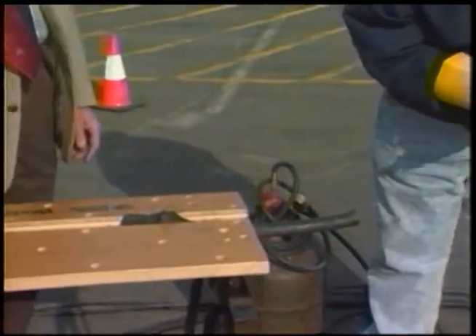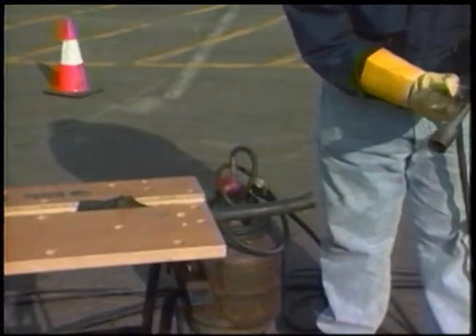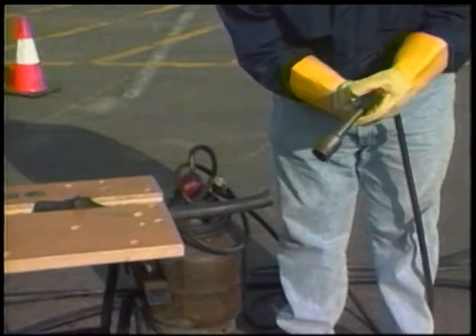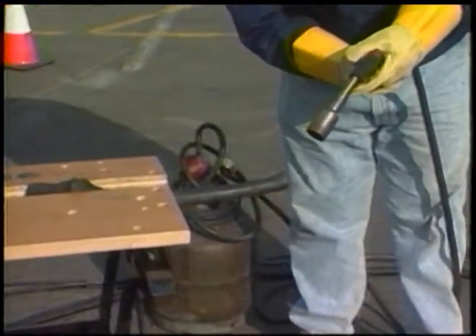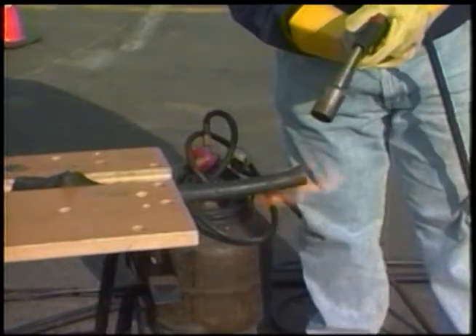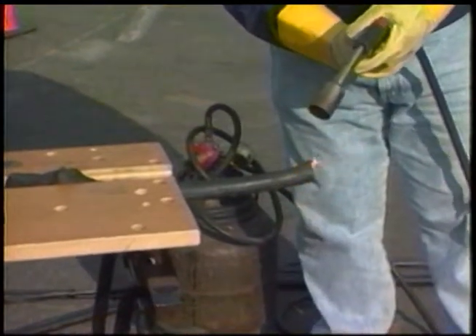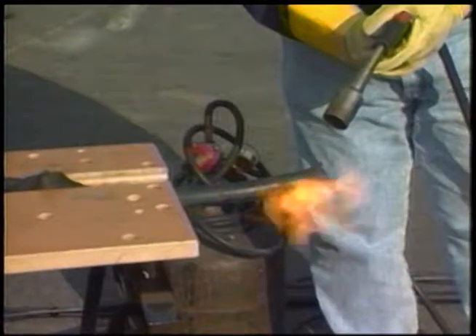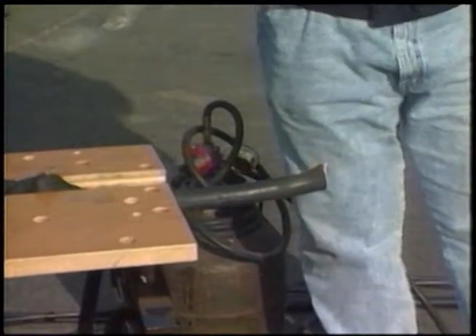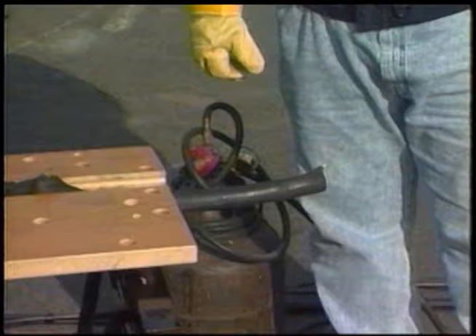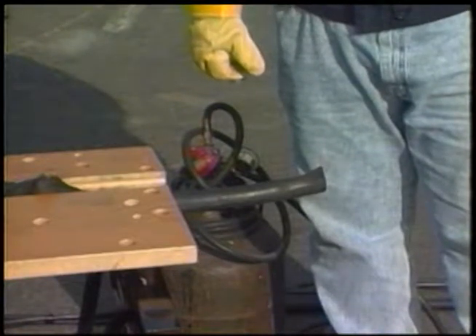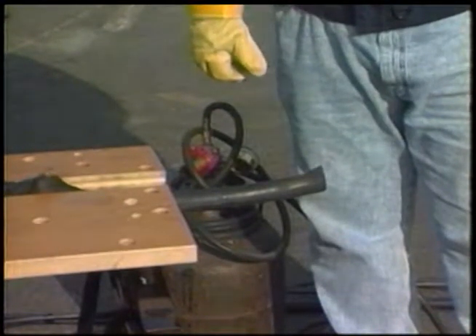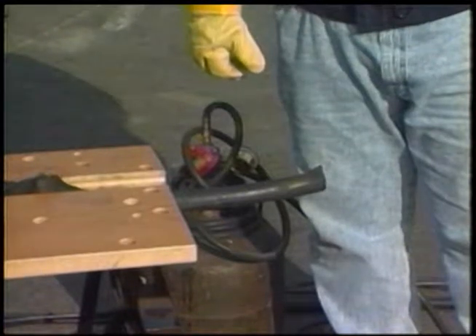We have replaced the old cable, the paper and lead cable, with the new fire-resistant cable. We'll now see how well that burns. Now this is about the same length of time that we had the paper and lead cable on. Now, Kurt, if you take that away, let's see if it continues. Now you notice the flame is getting smaller and smaller and finally goes out, whereas the paper cable continued to burn along the length. Okay, let's try it once more, Kurt.